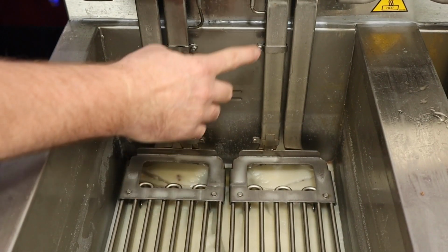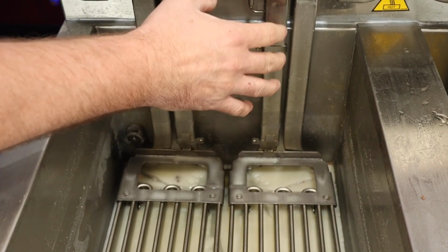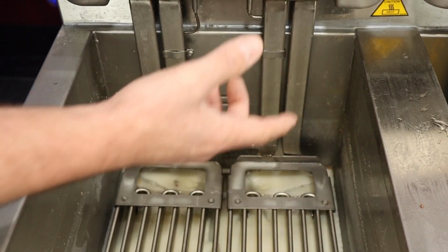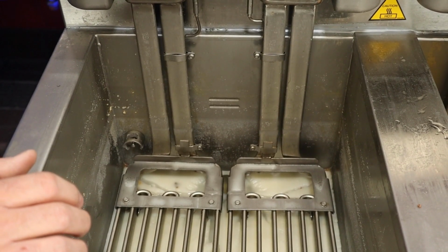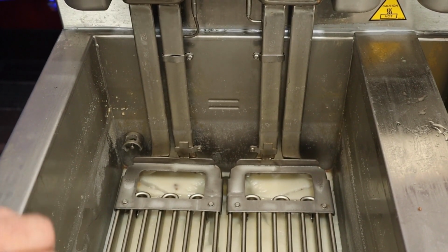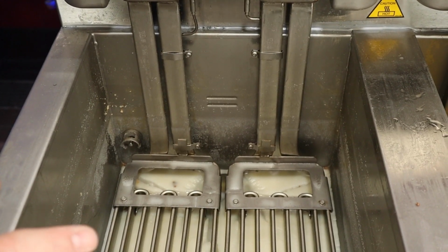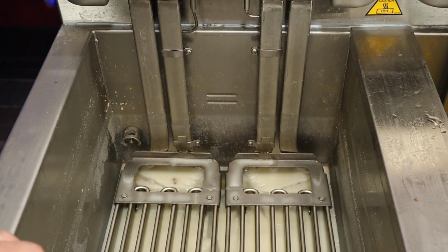So of course, if it's not the high limit probe and if it's not our elements, it could wind up being the high limit PCB, but we would want to check those components first. So then that's how we would troubleshoot the E10T as in Tango and what that would look like.